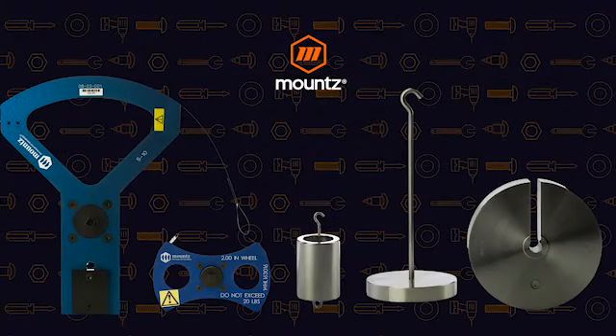So the calibration equipment that you would need if you want to do this type of testing in-house are going to be segment arms, wheels, weights, hangers. This is the type of equipment that you would need, as well as a way to position or a bracket to hold the sensor or analyzer that you may be testing in, that we would be able to actually implement the use of the hangers and weights.